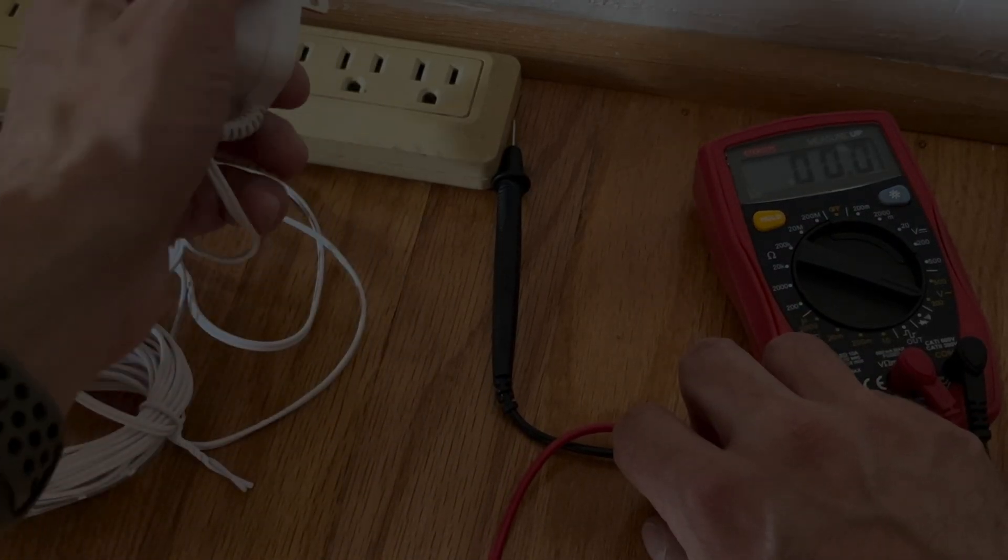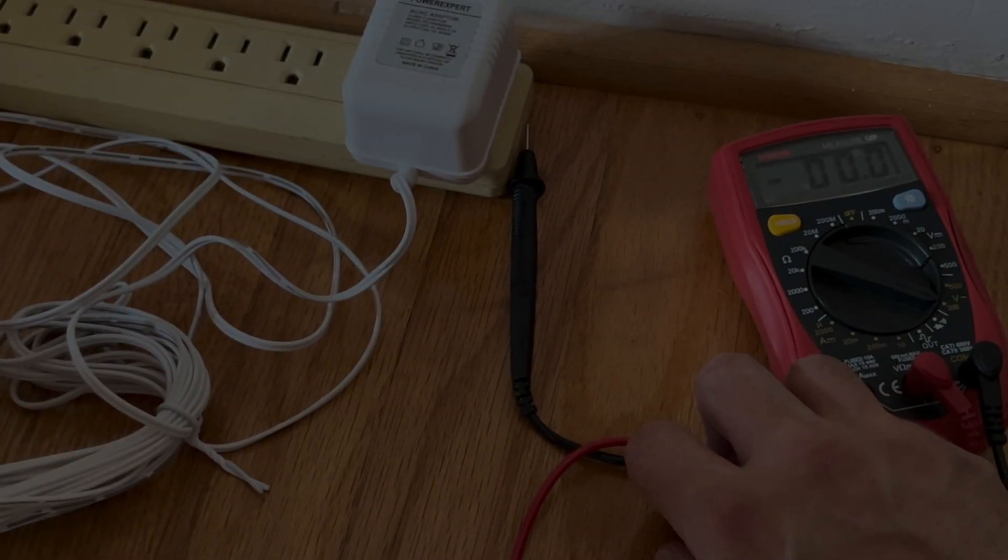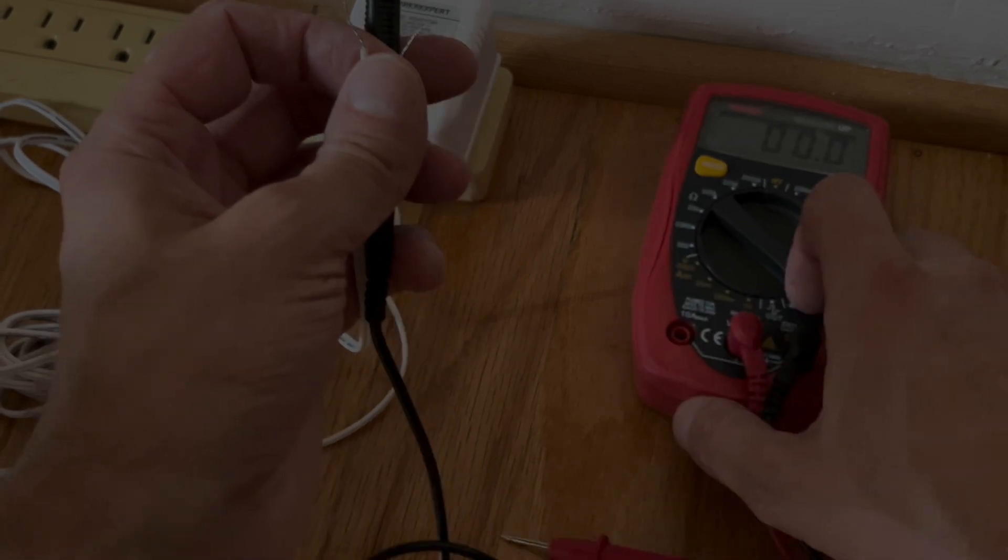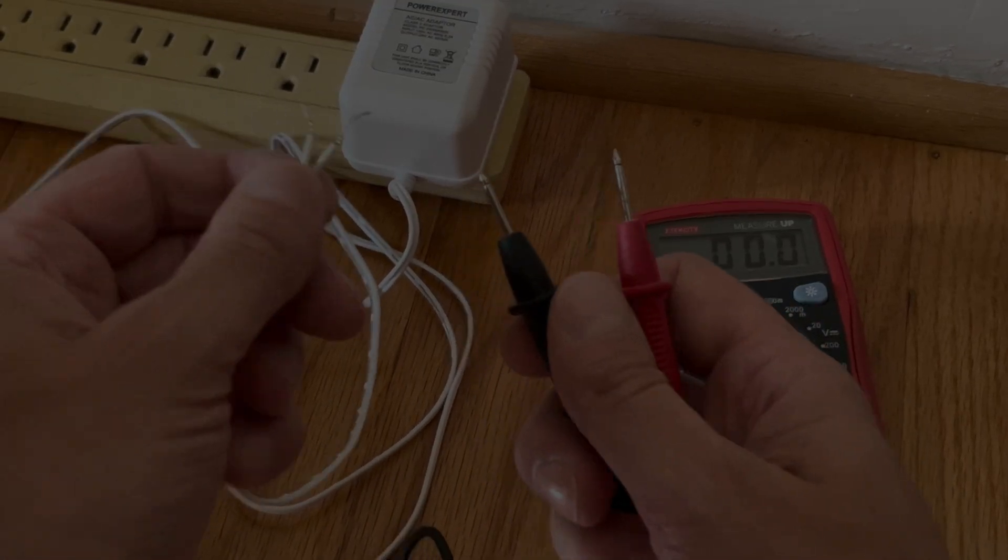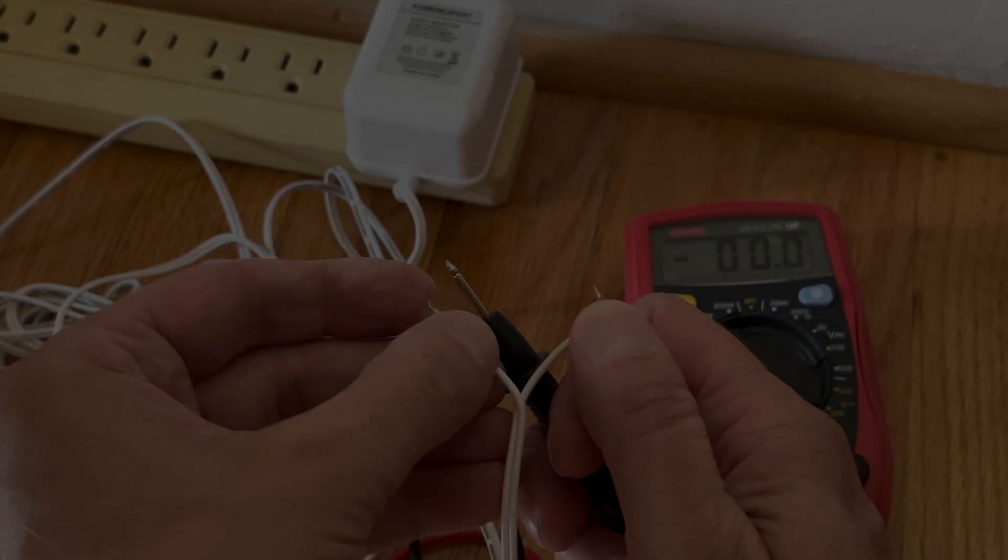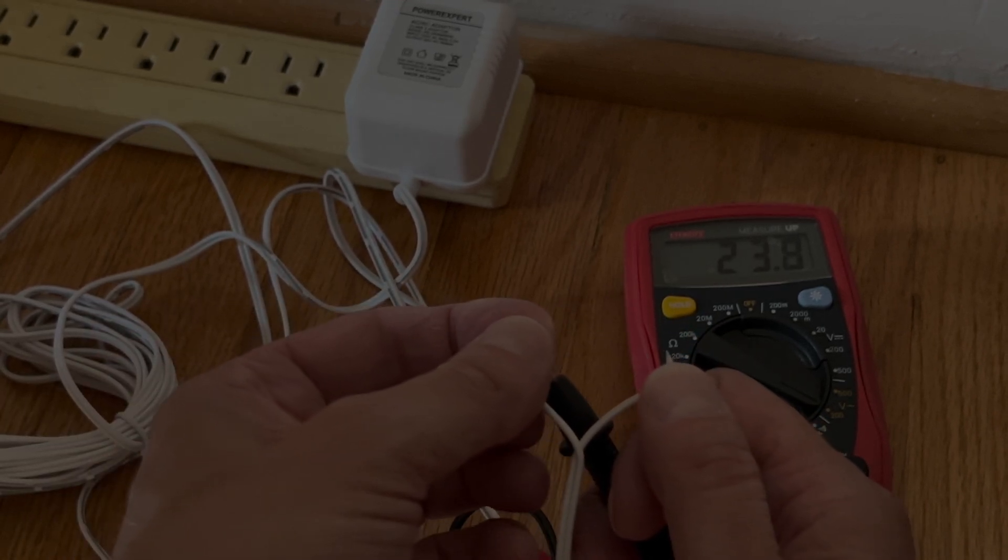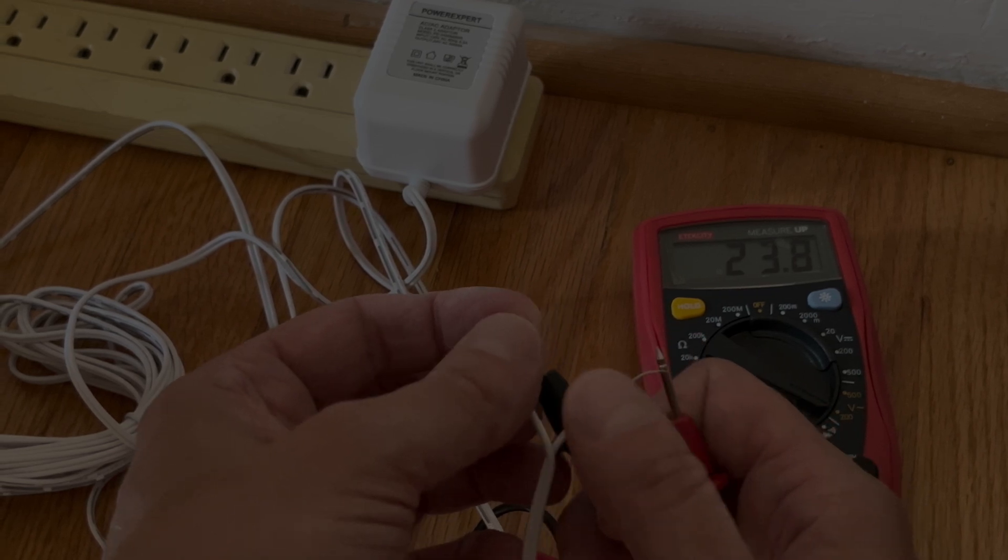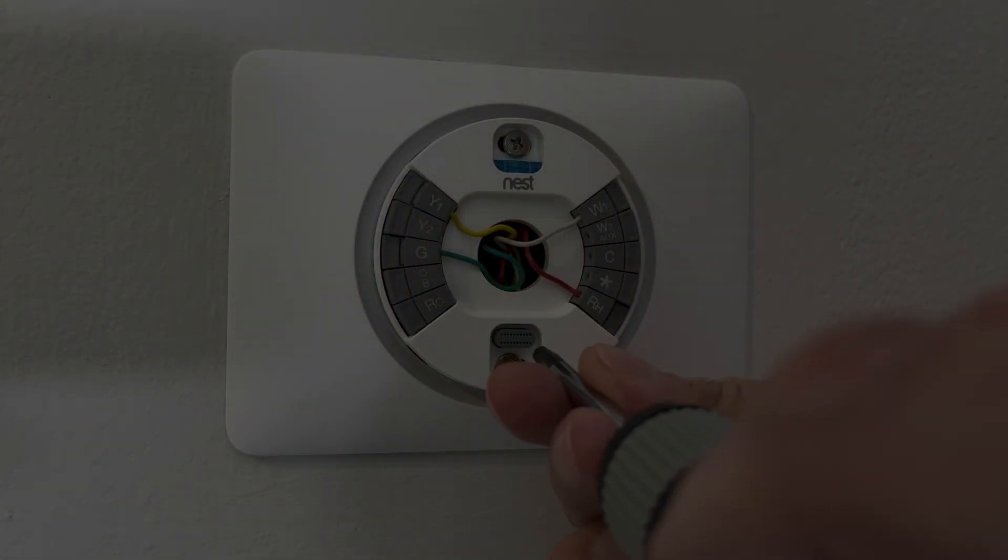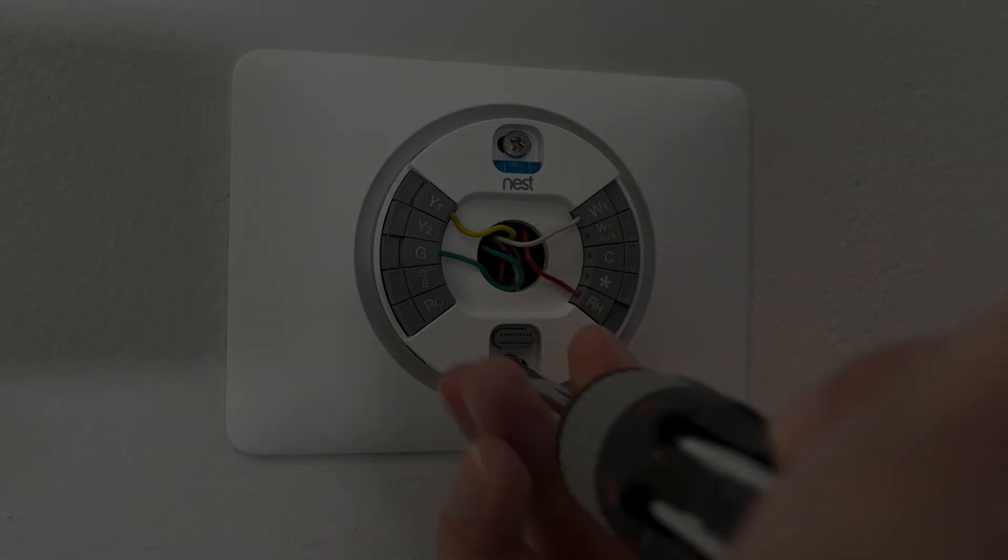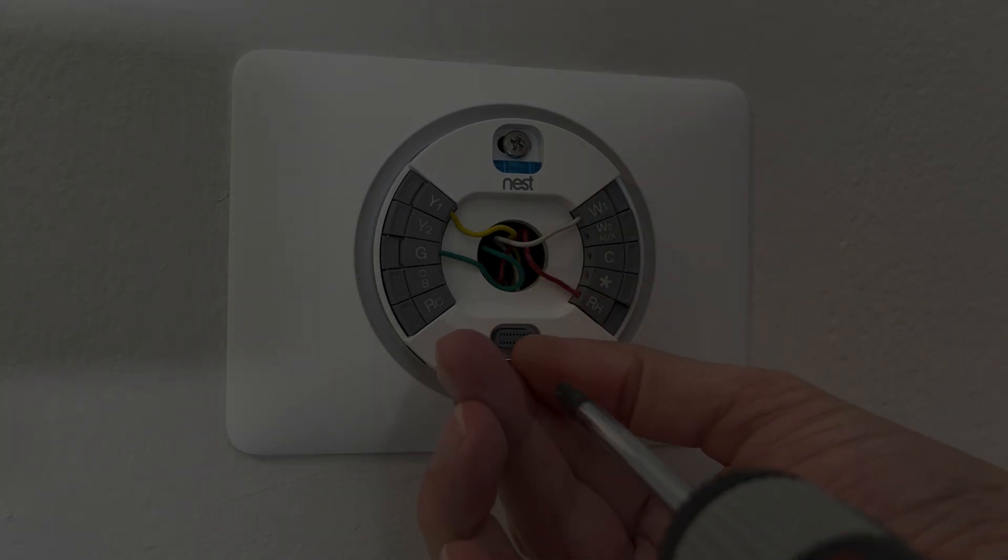The first thing that I'm going to do here just to make sure is I'm going to make sure that this actually works. So I'm going to use here my multimeter and I'm checking here that we're actually getting here the 24 volts. So we see a 23.8, that's very sufficient. So this power supply is functioning properly and we can use it and install it right now.